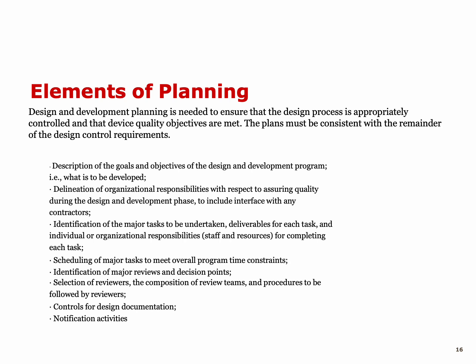So when you produce a document which is related to planning a medical device, we will need to have this document in writing, because if it's not in writing, it never happened. So we need to show to inspectors who are coming, and of course when you're also going to apply for the registration of our medical devices, we will need to have enough documentation proving that from day zero, where we started to have our project for this medical device, we have been following the rules and regulations, and we need to have documented proof that we have been in compliance with these regulations.